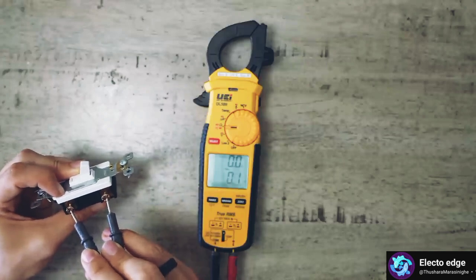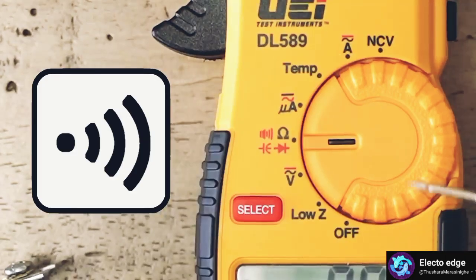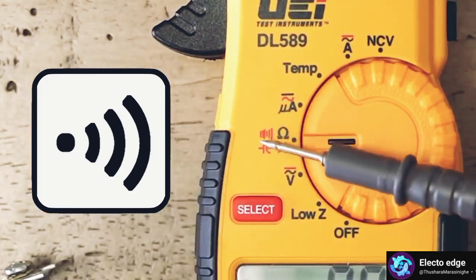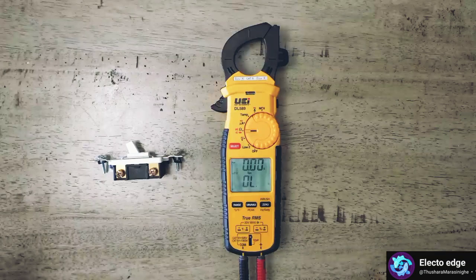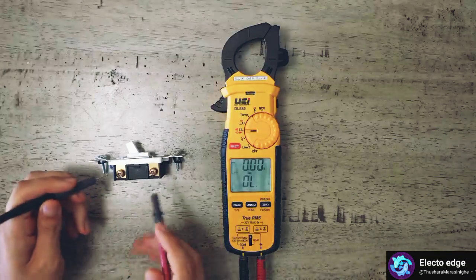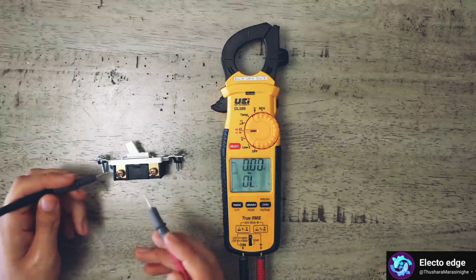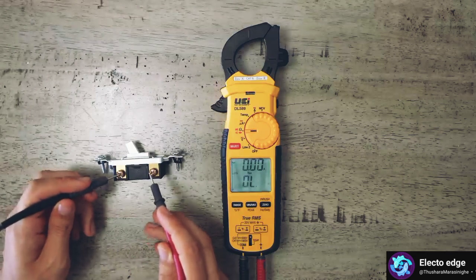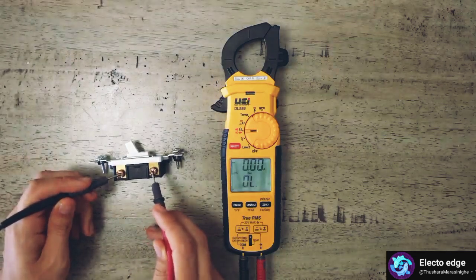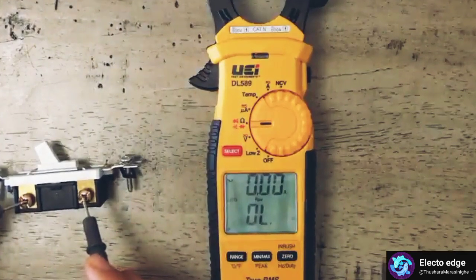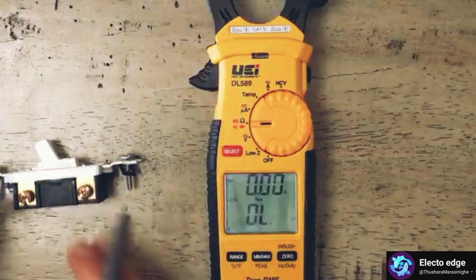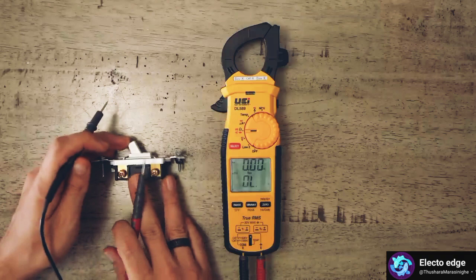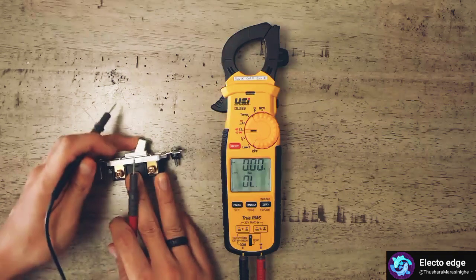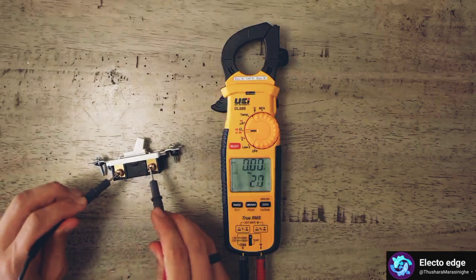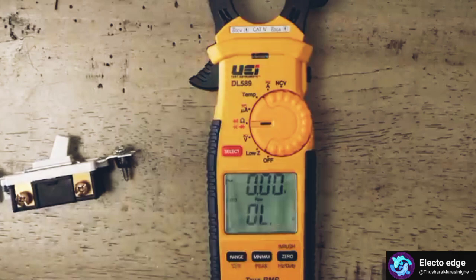Another really useful feature is continuity, which is this symbol right over here. Checking continuity is similar to resistance, but the meter is also going to beep if there's a connection between the two points. So if I put my meter leads on here, we're not hearing anything. That's because the switch is open. But if I close this switch, put it in the on position, now we're hearing a beep.